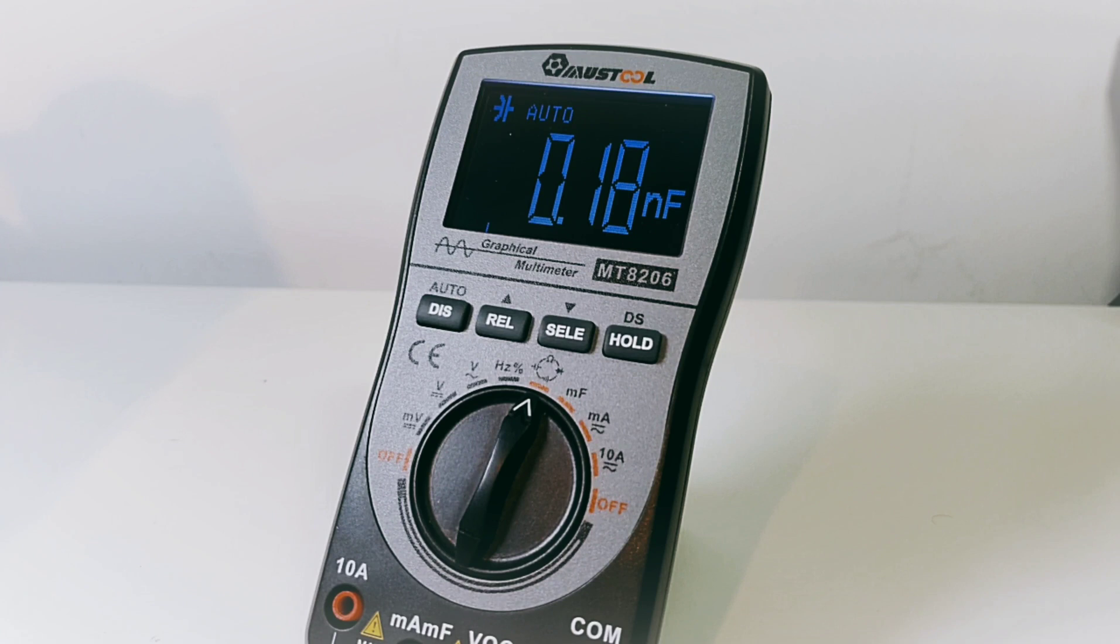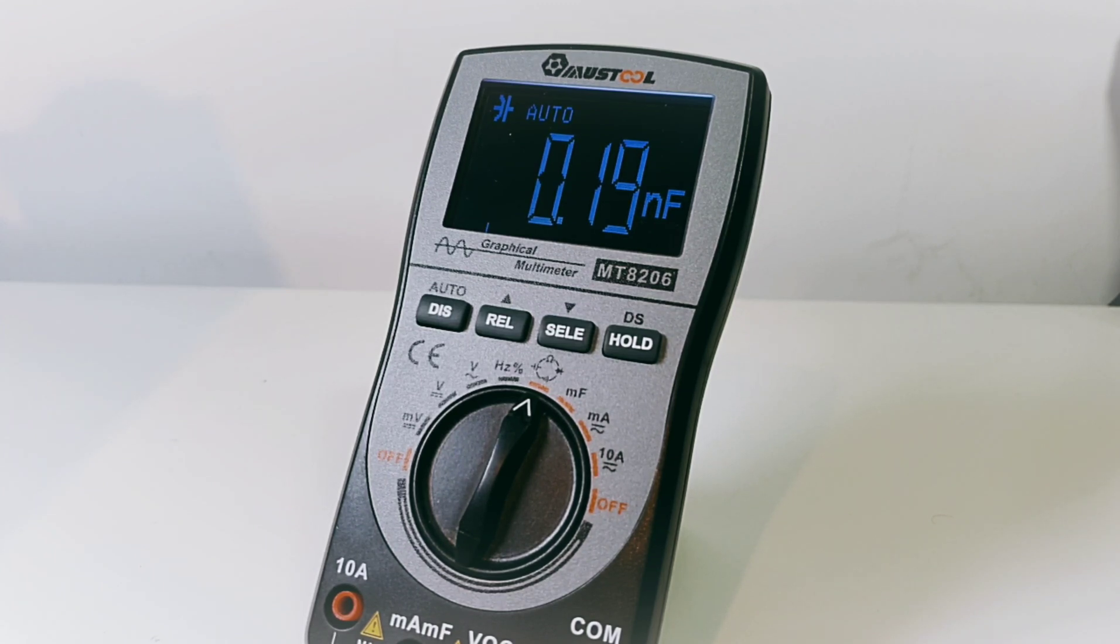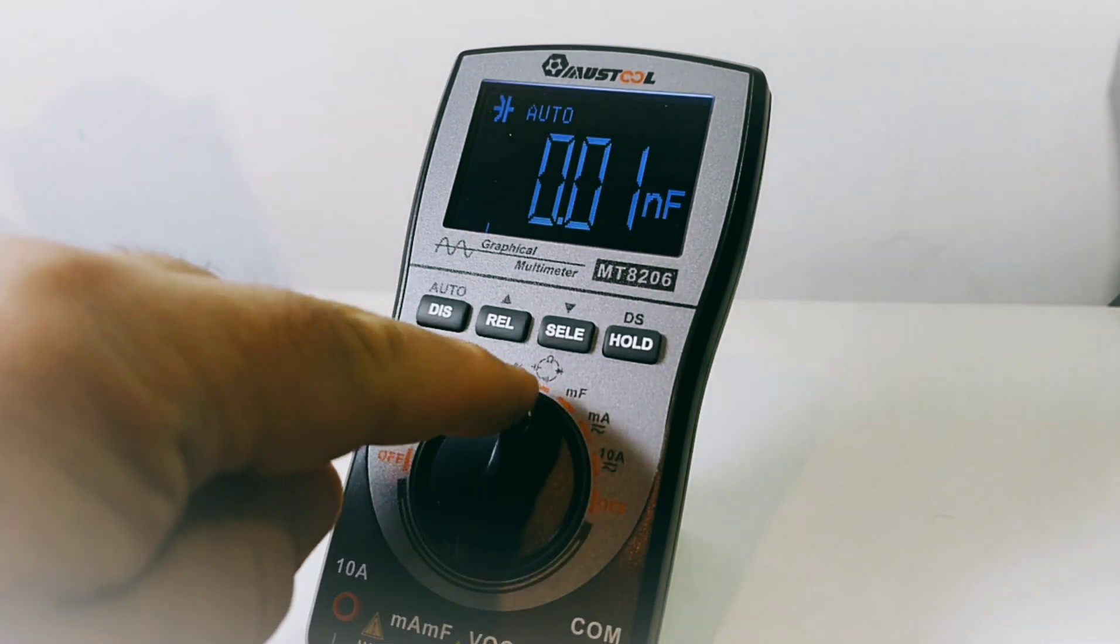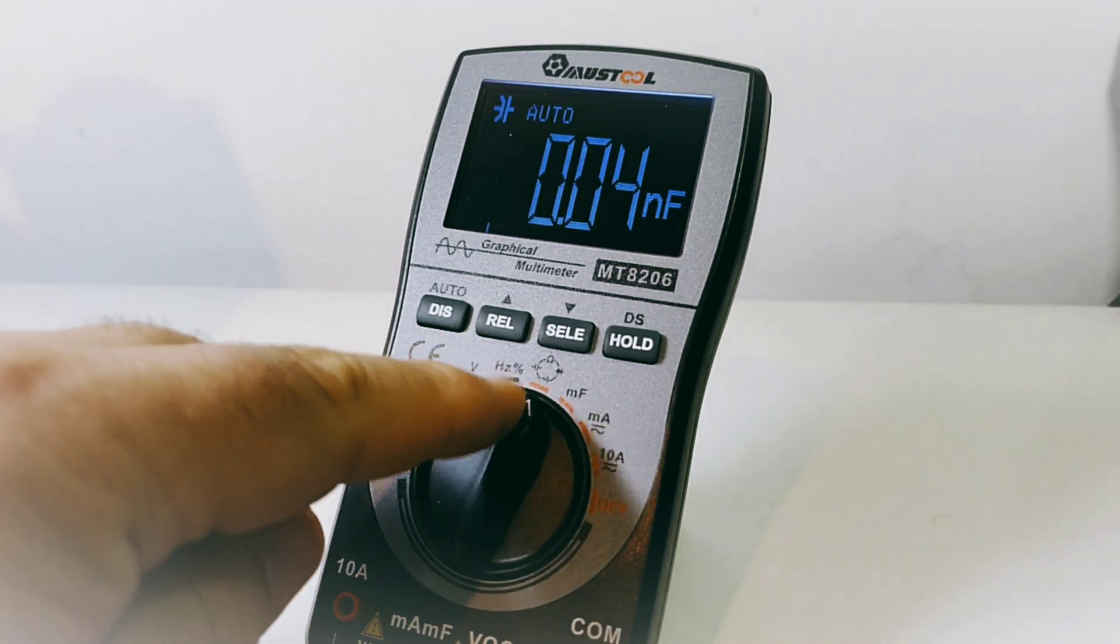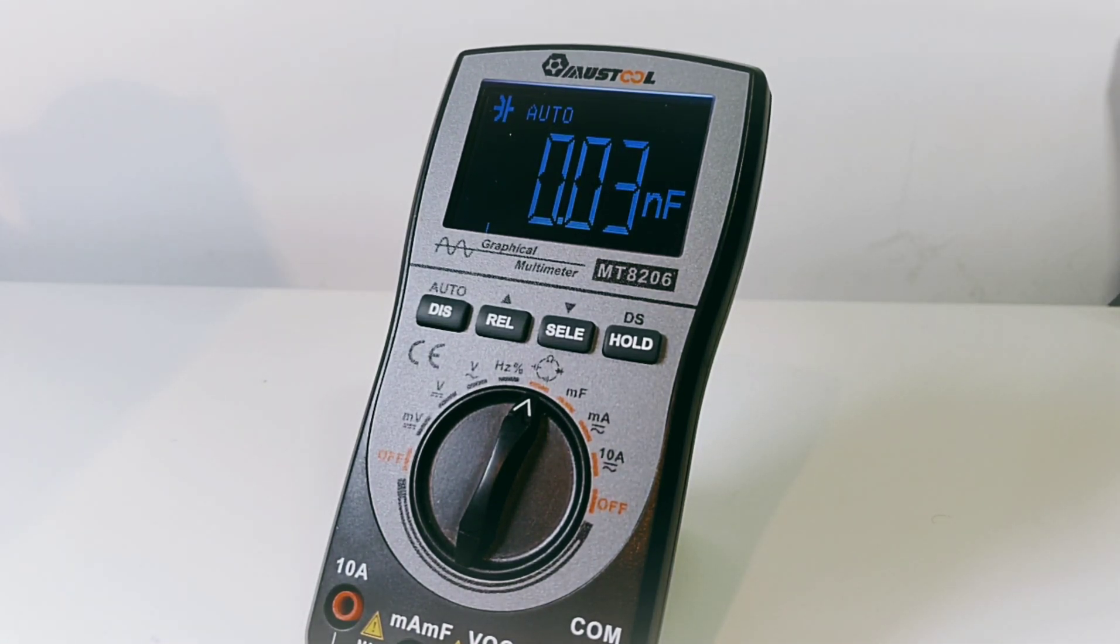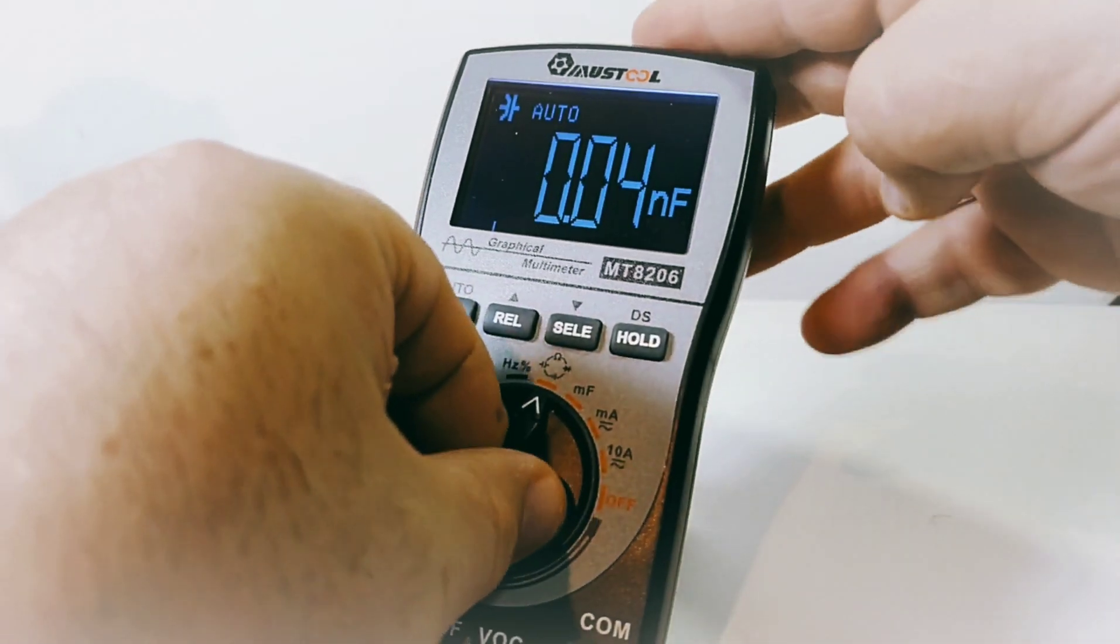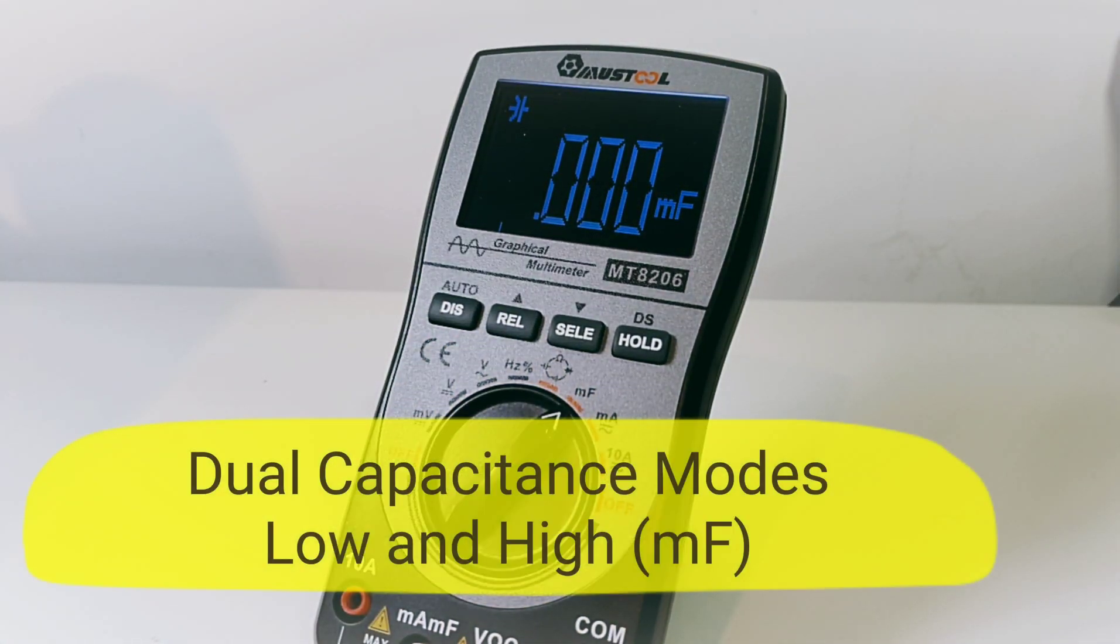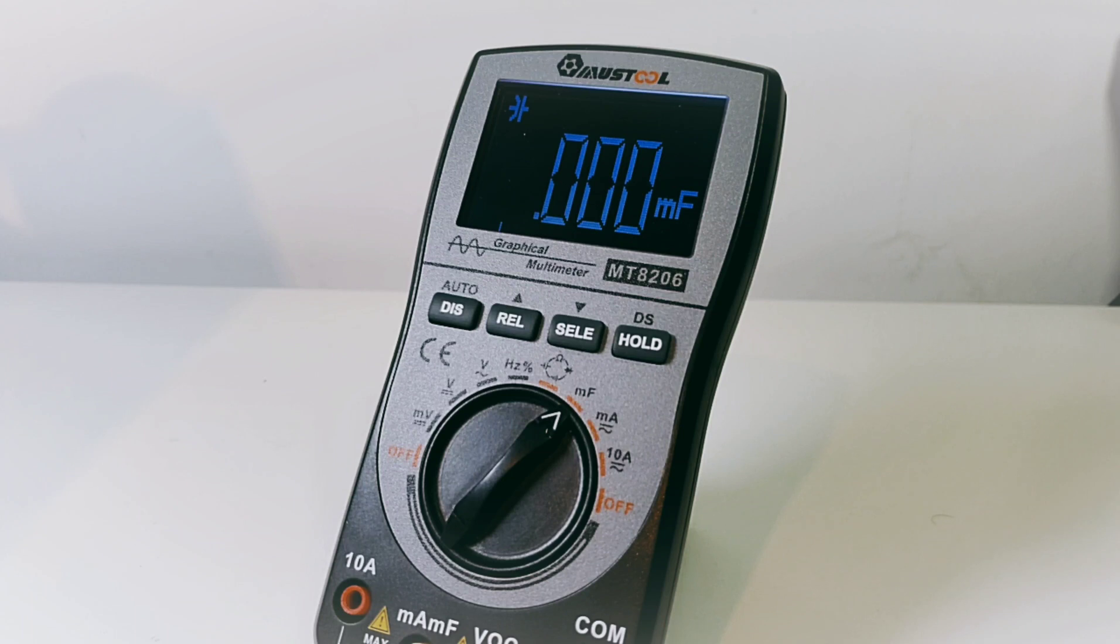Now the MT8206 has a rather interesting capacitance mode because, yes, we are in capacitance, but in reality this meter is one of the few I've seen that actually has two capacitance settings. In the basic setting that we're in right now, sitting right on top of the diode, resistance, and continuity selections, in this capacitance setting it can do a maximum of 100 microfarad. Anything bigger than 100 microfarad, you actually have to switch it and go into millifarad mode. This is good up to 10,000 microfarad or 10 millifarad. A little bit different. I don't know why they have to utilize this dual functionality, but there you go.